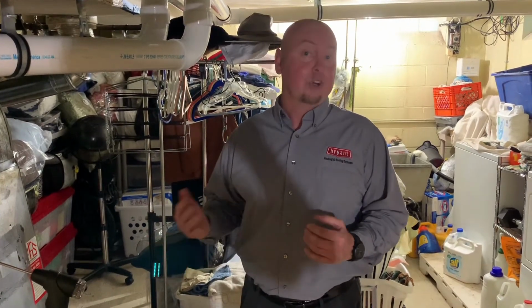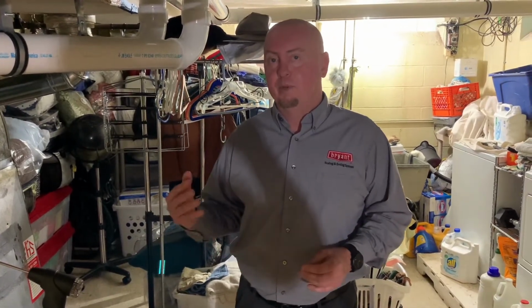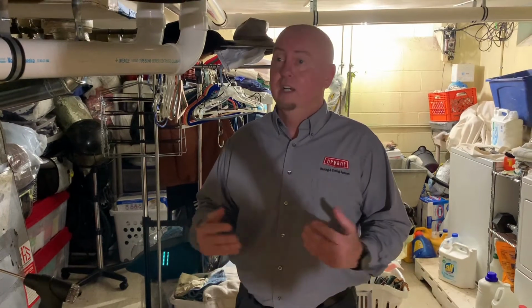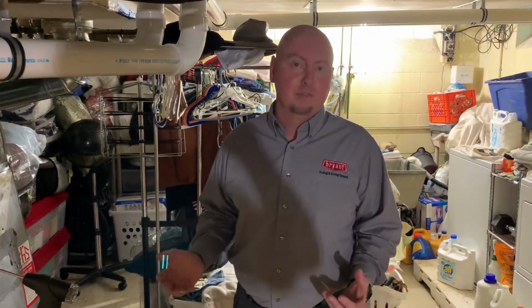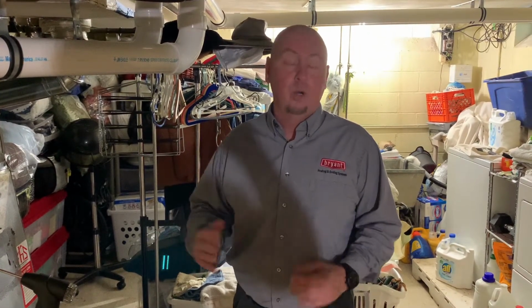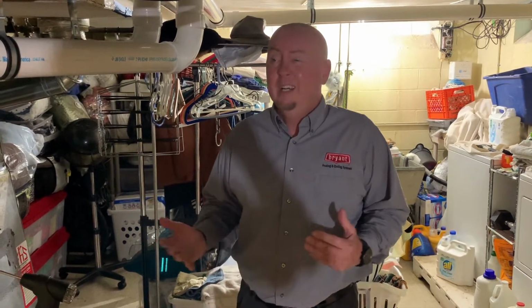That can be higher or it can be lower. You will find that number to be higher on things with short vent systems, 80-plus furnaces, things where you really can't control how much air is going through that. So it's not unusual to see 11, 12, something like that on O2 levels, which really just means, in a lot of cases, it could affect your lighting, it could affect the efficiency, things like that, but usually not a terrible situation.